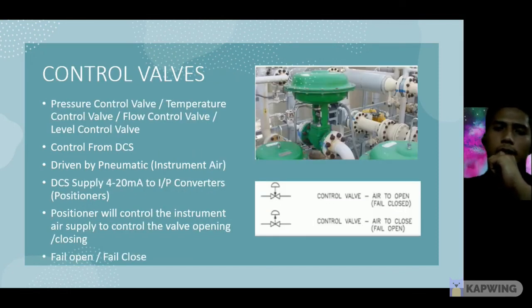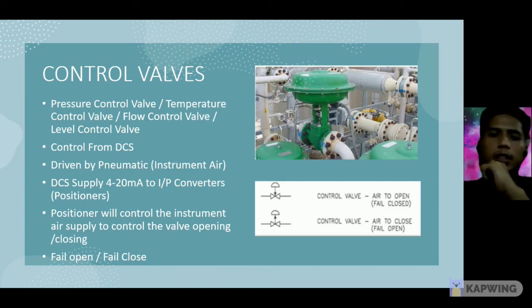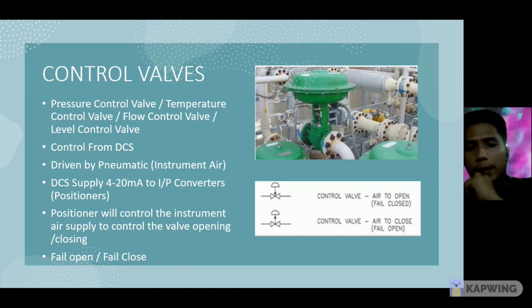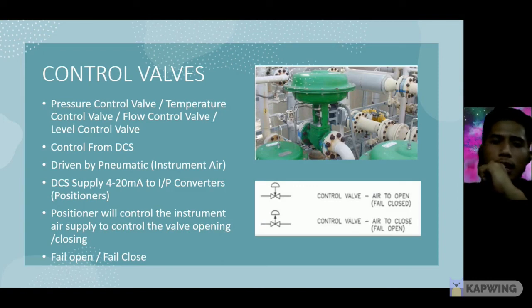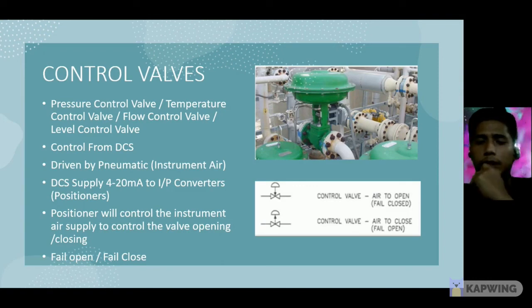And lastly is the control valve: pressure control valve or temperature control valve, flow control valve, and level control valve. It's controlled from DCS. It's also driven by pneumatic. The positioner will control the instrument air supply to control the valve opening or closing. It has two types, fail open or fail close. That's all from us. Thank you.